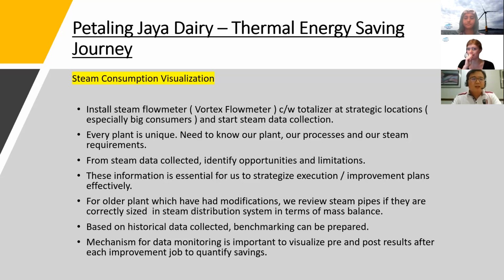Okay, thanks. Steam consumption visualization. Install steam flow meters, usually vortex flow meters, which come with a totalizer, at strategic locations, especially for big consumers, and start steam data collection.